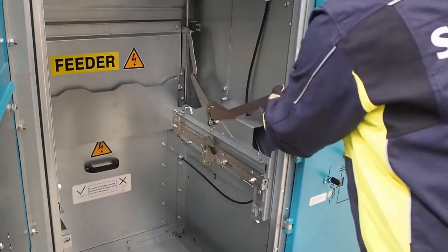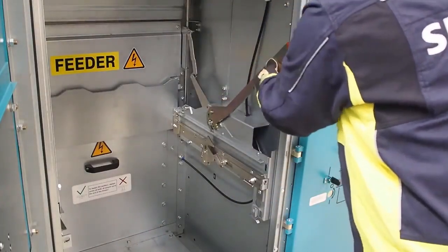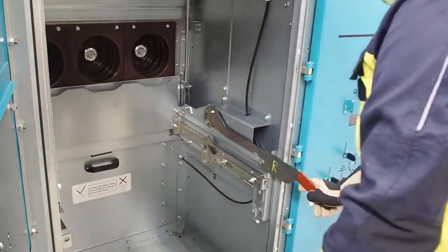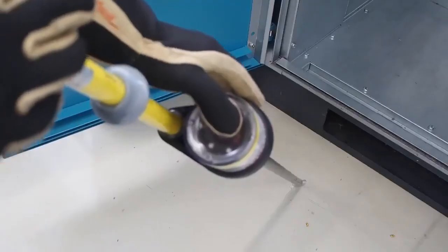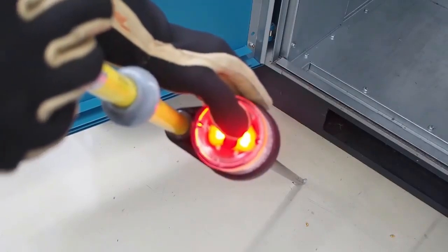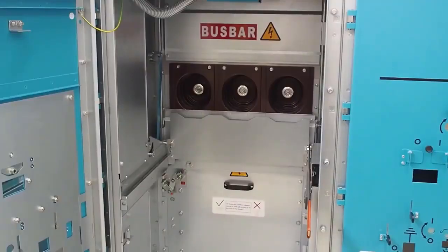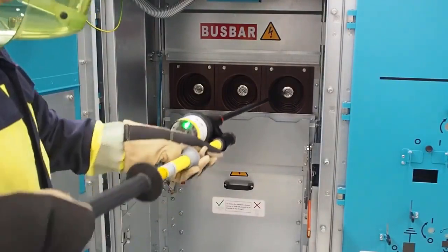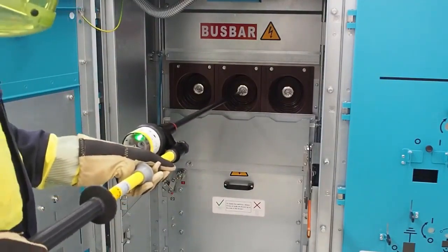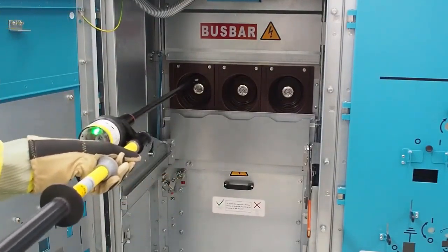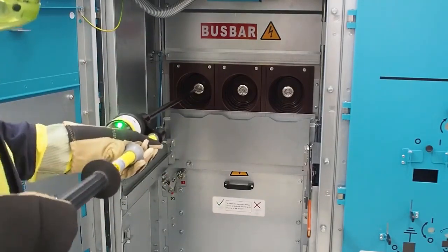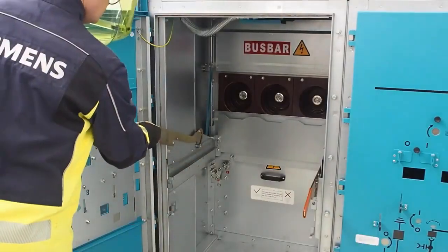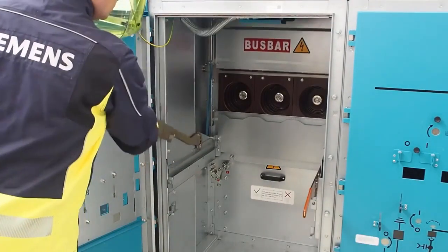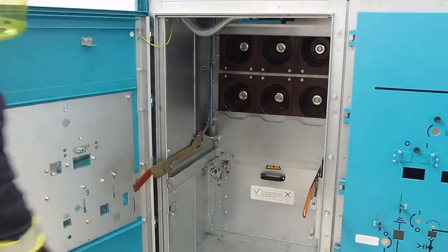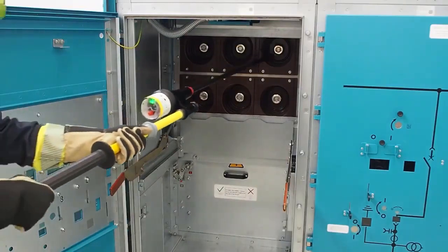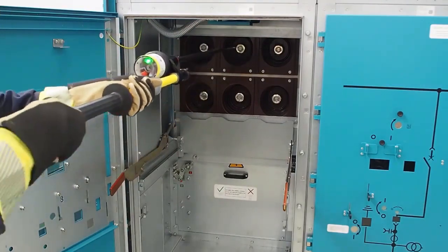Open the lower shutter of the feeder and check if the high voltage tester works properly. Verify that the lower contacts of the incoming and cable feeders are free from voltage. Then open the upper shutter of the busbar. Finally, check that there is no voltage across the upper contacts of the busbar.